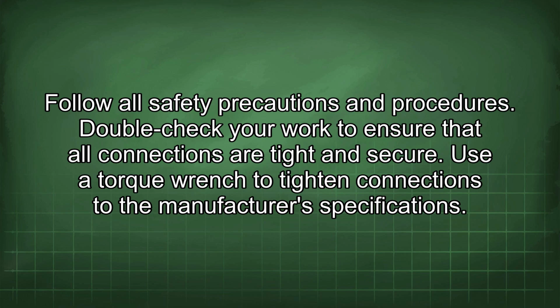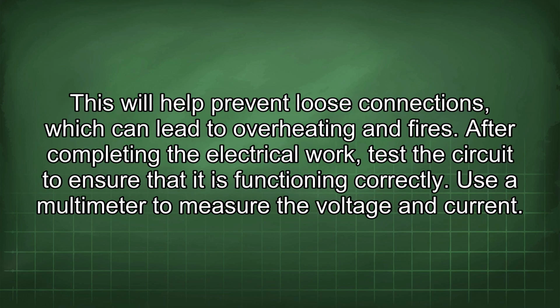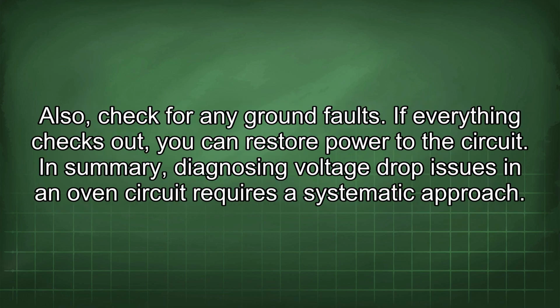Double-check your work to ensure that all connections are tight and secure. Use a torque wrench to tighten connections to the manufacturer's specifications. This will help prevent loose connections, which can lead to overheating and fires. After completing the electrical work, test the circuit to ensure that it is functioning correctly. Use a multimeter to measure the voltage and current. Also check for any ground faults. If everything checks out, you can restore power to the circuit.